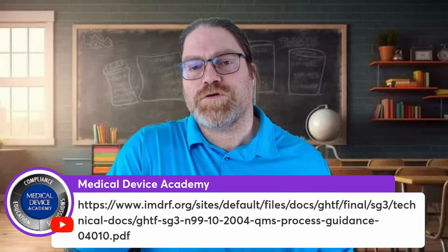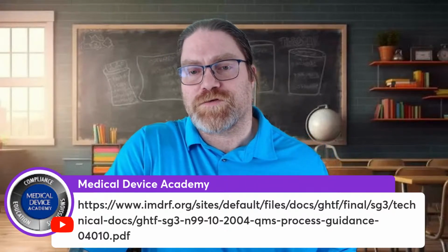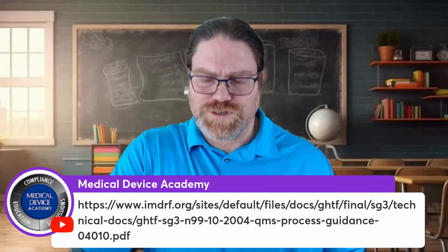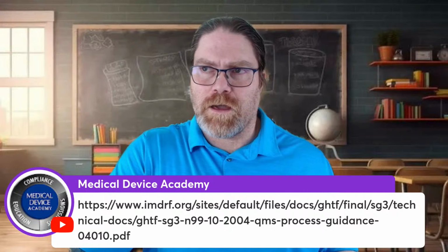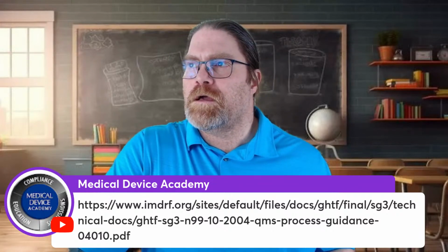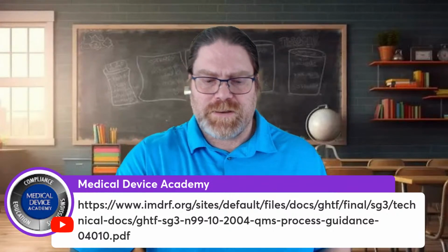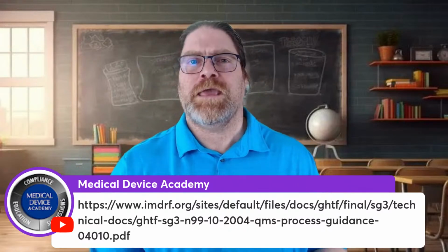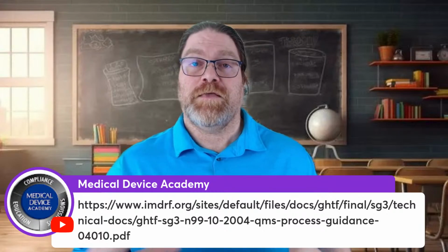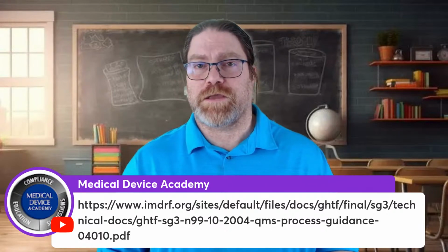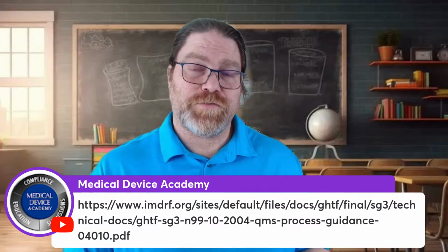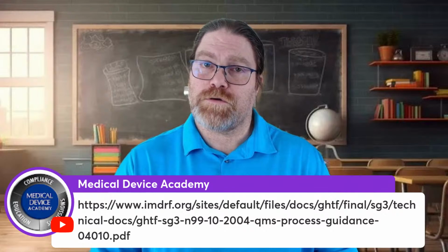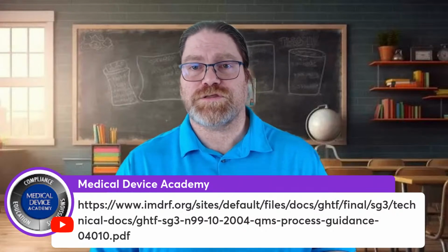And then the only thing they really have to do is create a summary at the end to go with it. But if you're looking for what the FDA's minimum requirements are for a summary report of a validation, they actually have published that, so you can look under non-clinical report requirements or something. But FDA non-clinical report guidance is what I would probably type in, and that should get you the guidance document that tells you what the minimum requirements are and what they're looking for in a report. So if you have all those things in your report, it meets the requirements. So that's how you do an IQ, OQ, PQ. I've given you some resources that you can hunt down.